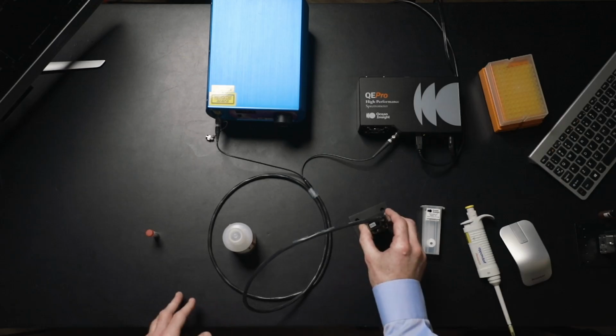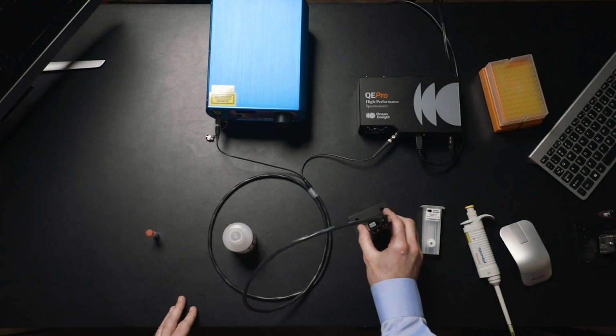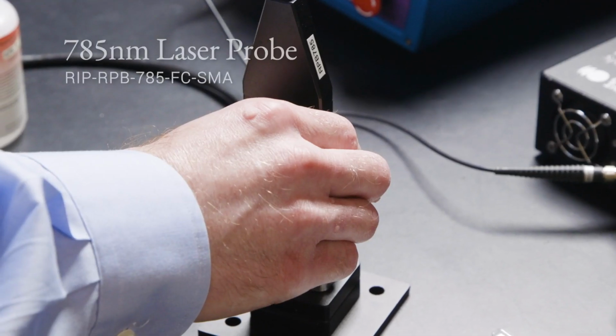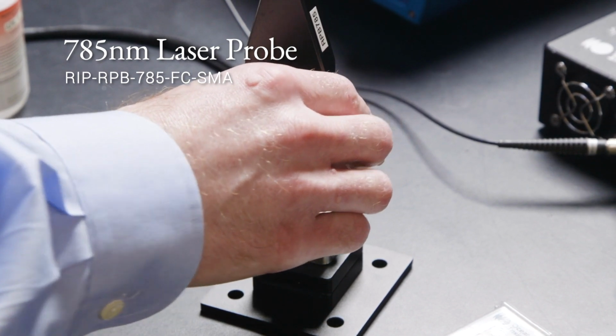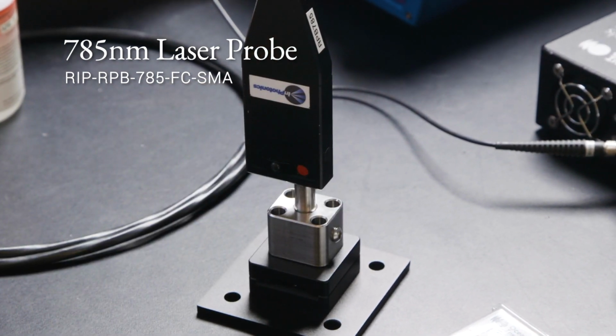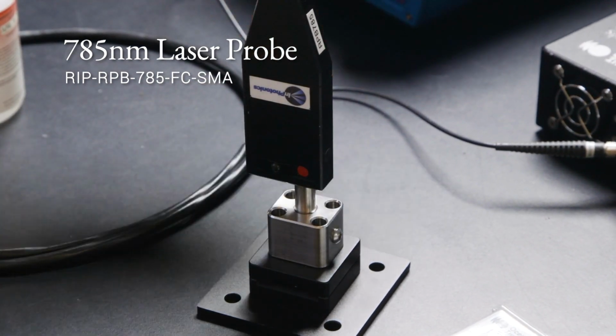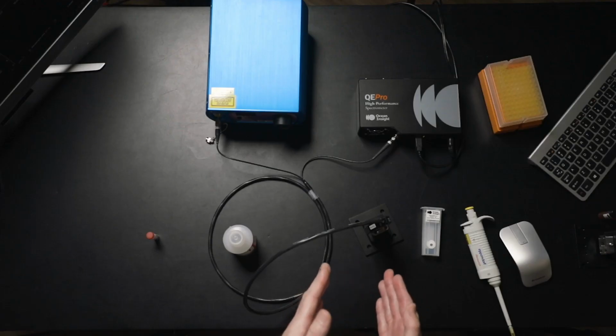And this probe that we're using, this is one of our standard 785 nanometer laser probes that has individual fibers to run to the laser and then also to the spectrometer. And this is going to attenuate the power from the laser a bit, so that's why we can't just take the laser power directly from the laser, but we're actually taking it out of the output port of the probe itself.